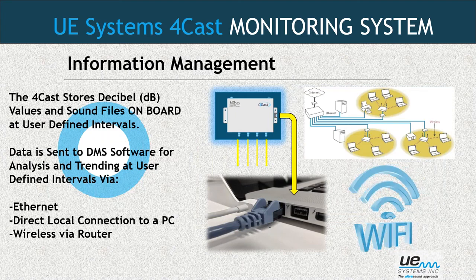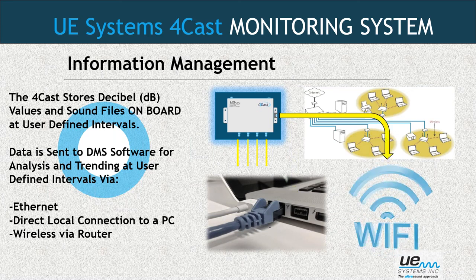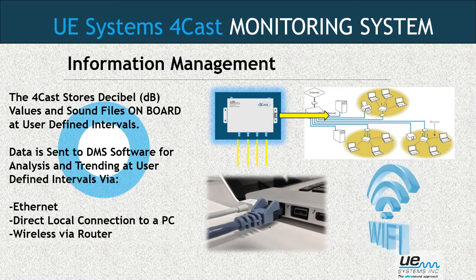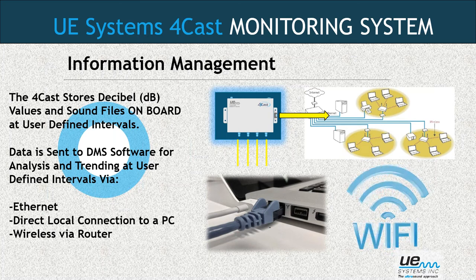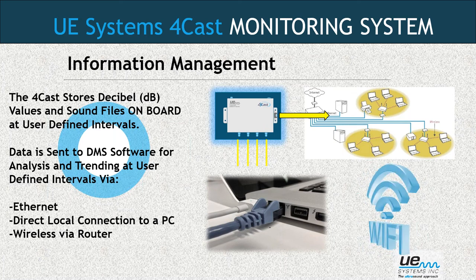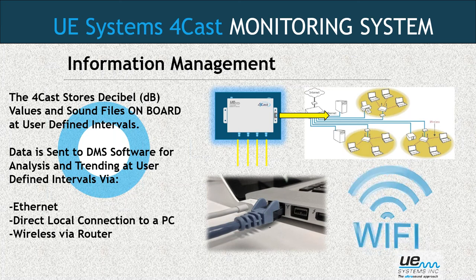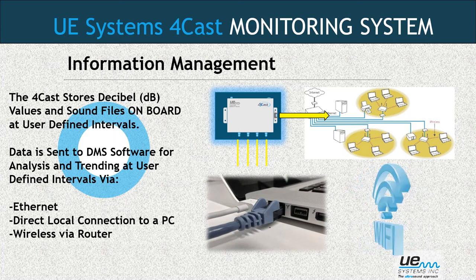So the 4Cast stores these dB values and sound files right on board the unit at user-defined intervals. So once we've got that information to send over to the DMS software for analysis and trending, we have a couple different options. We have different ways we can get that information out of the box and over to our PC for a permanent record. One is an Ethernet connection. You simply have an Ethernet port on the box, you hook it into the plant's Ethernet, and however often you've told the box to do so, it sends it over for a permanent historical record.